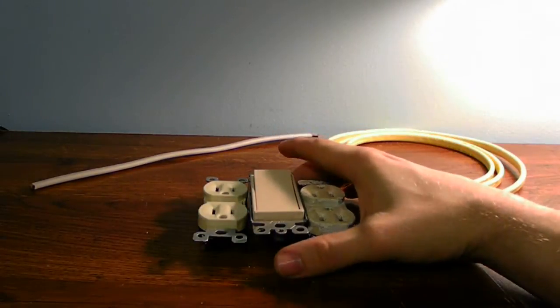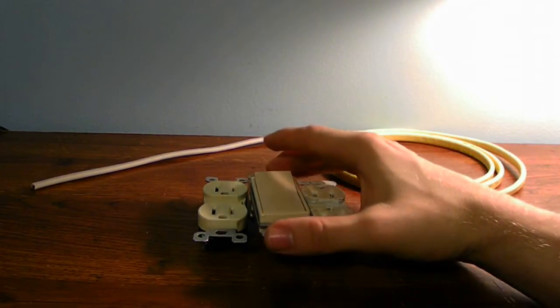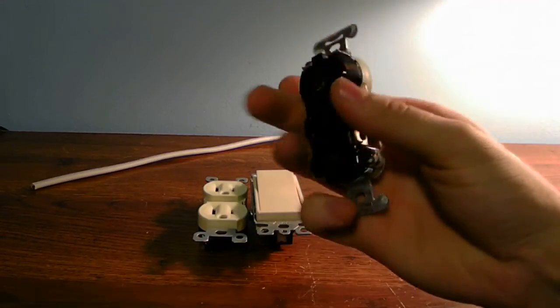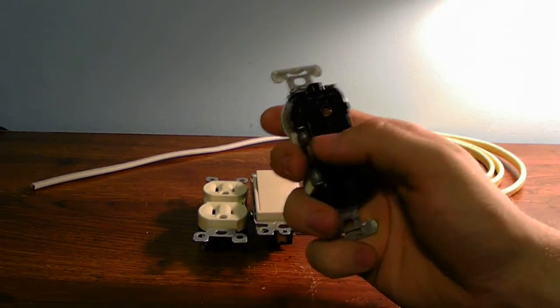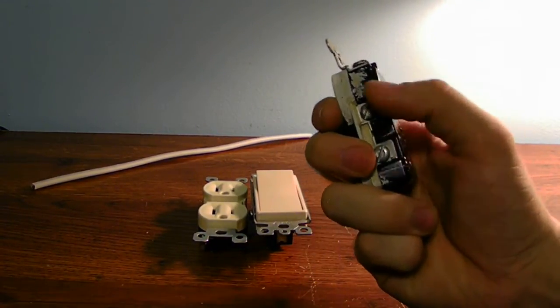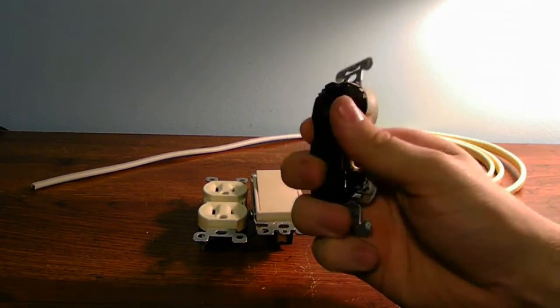But the reason why I don't like using the push-in terminals on the switches and outlets, because one thing, they will short out when you push them into the wall. And once you take them back out, the push terminals will come eventually loose. The screws are a solid connection.